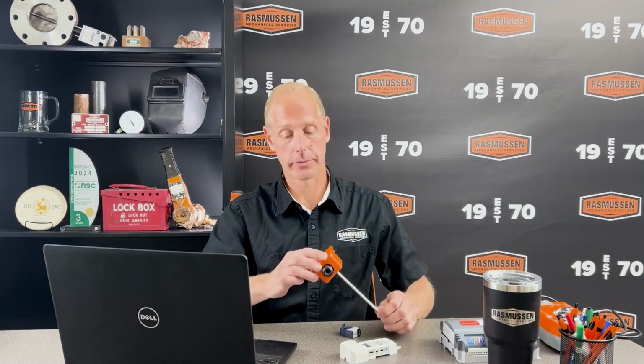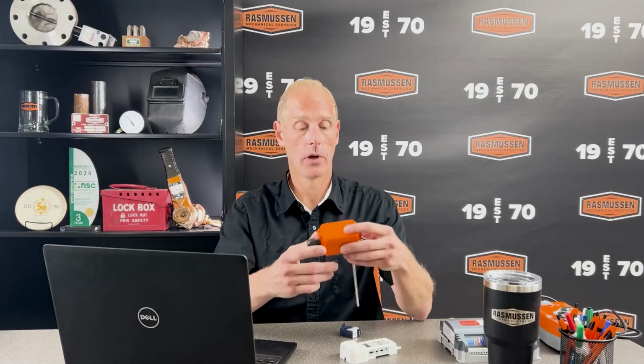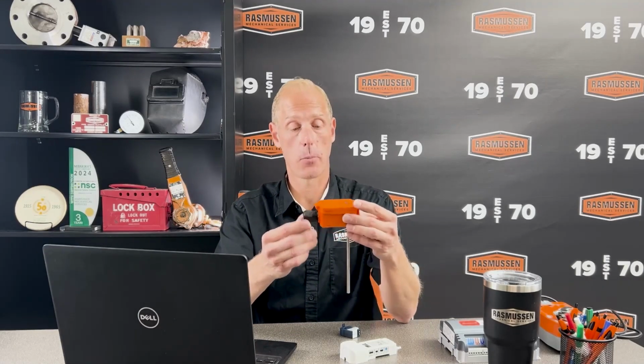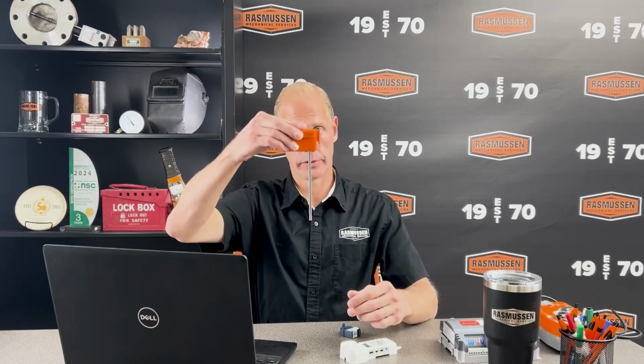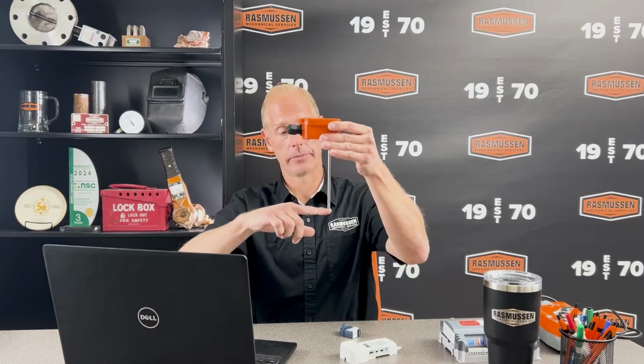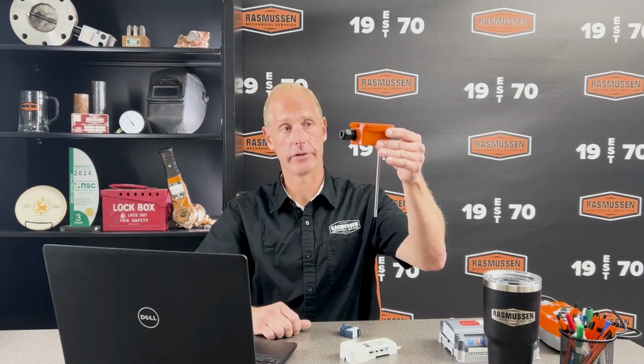We have digital inputs and outputs. We have analog inputs and outputs. So I have some sensors here to show, for example. This one right here is a very basic temperature sensor. This is a probe style sensor. So this is meant to sit on top of ductwork, and this probe will be down in the ductwork to measure the air temperature going through that duct.